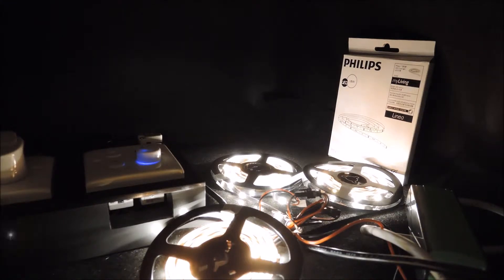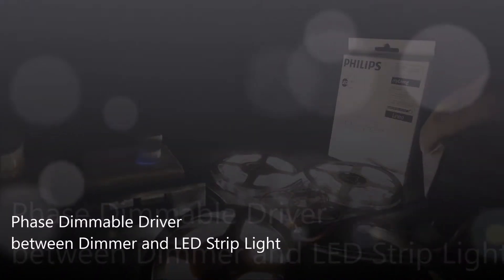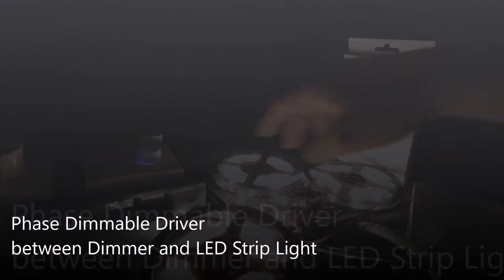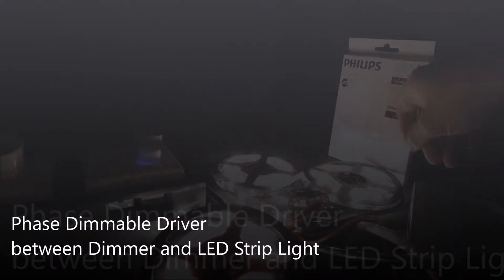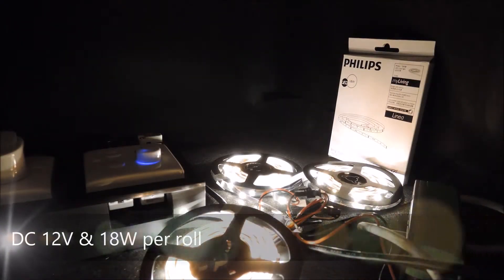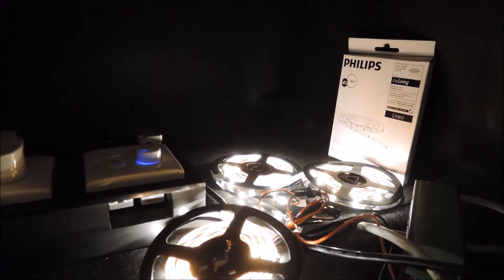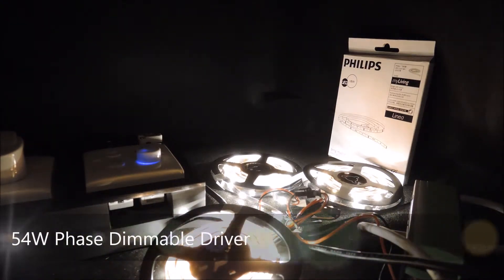To support the demonstration, our team has also built a phase dimmable driver that's now connected between the DIM-Easy dimmer and the LEDs. Each roll has a specification of 12 volt DC and 18 watt, meaning that the driver needs to deliver three times 18 watt, or a little more than 54 watts in this case.